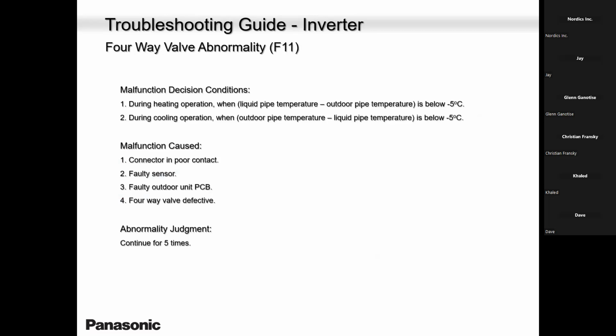I'm going through these slides, guys, because they show you what to do when you have issues like that. Basically F11 is a four-way valve. In most cases, if it's an old unit installation, it's the indoor sensors that got messed up. They have gone weak, and they're throwing you an F11 error code. In one or two cases, the four-way valve coil plug was pulled out. I don't know, maybe during shipping, but the plug was dangling and they were getting an error code.